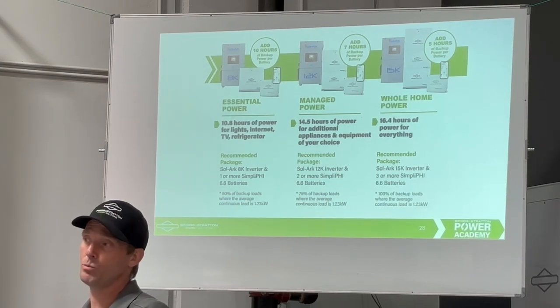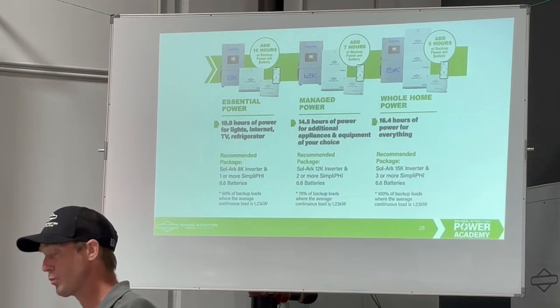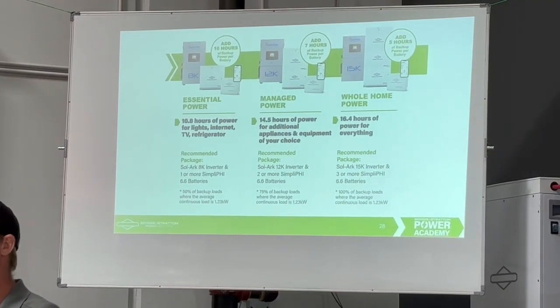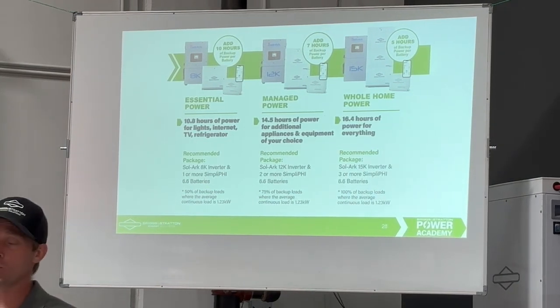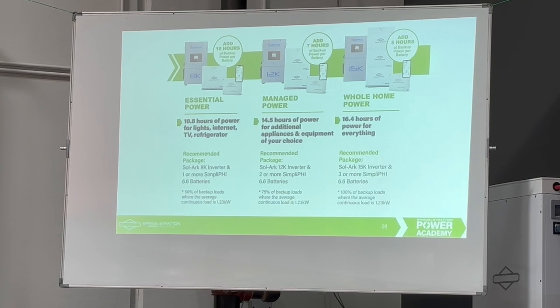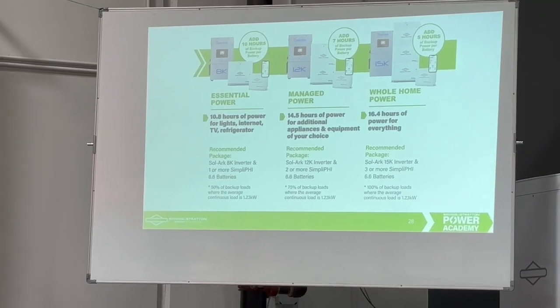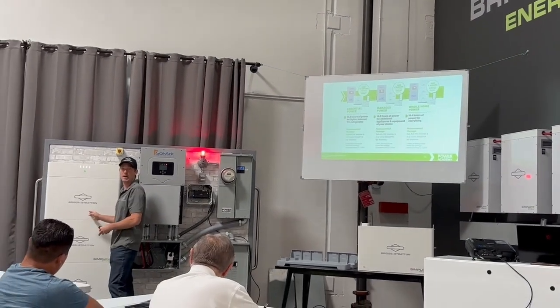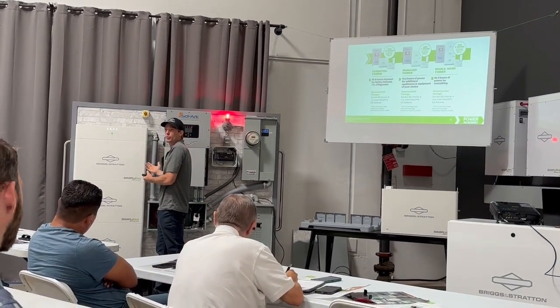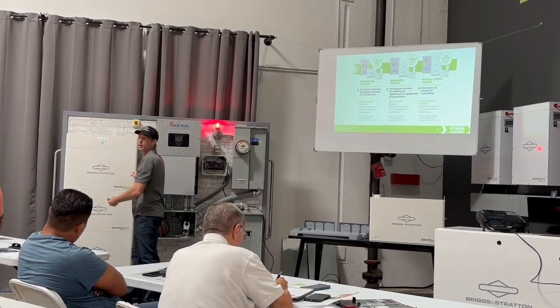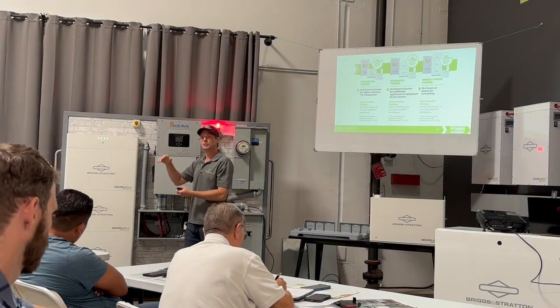That's a really important selling point for us. If you want to back up with a power wall, you can, but the inverter is integrated into the power wall. Right now I know they're supposedly coming out with a power pack similar to this, where you can do batteries separate from the inverter. But right now, if you want more storage, you've got to buy 2 power walls and increase your power and energy at the same time. With us, you could have a small battery because you just want a very short amount of backup time, but you could have multiple inverters, or you could have a very large battery bank with just a single inverter. So you scale the energy separately from the power.